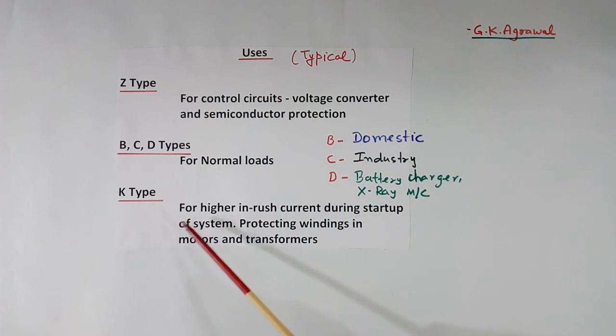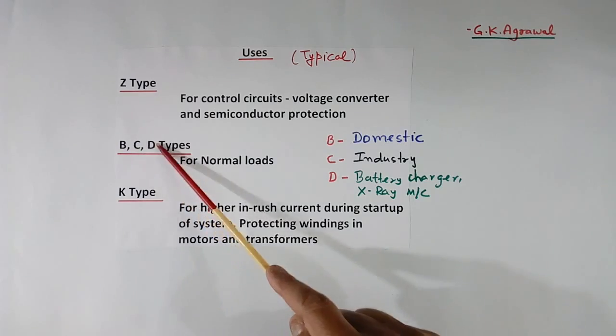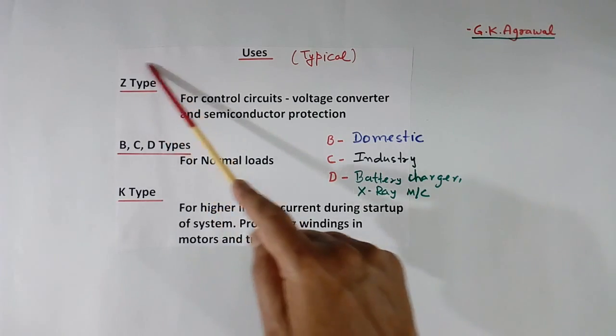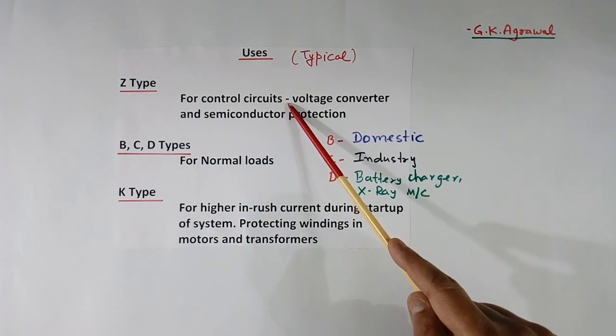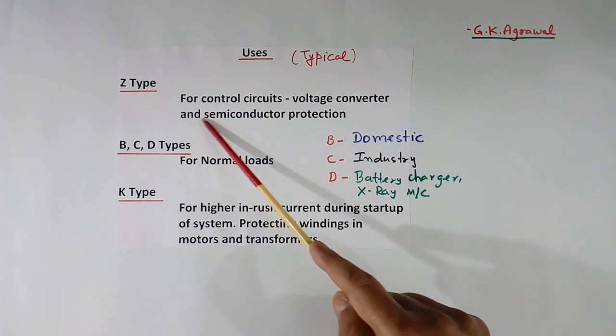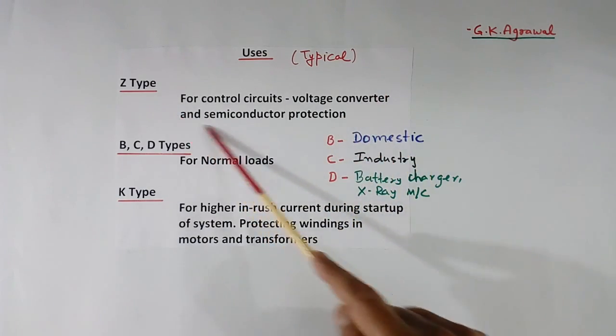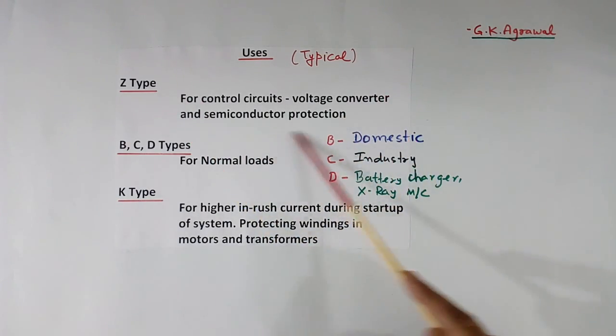Usage: I have told about 5 types of MCB - B, C, D, K and Z. These are typical usages. Z type is used for control circuits, for example voltage converters and semiconductor protections. Just now I gave a design example for this type only.